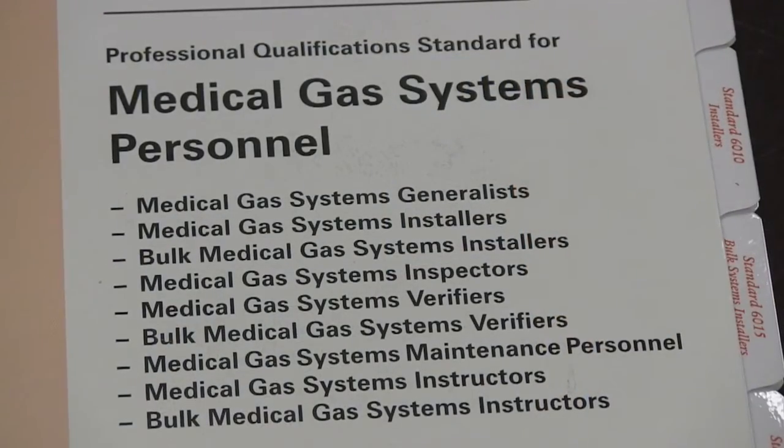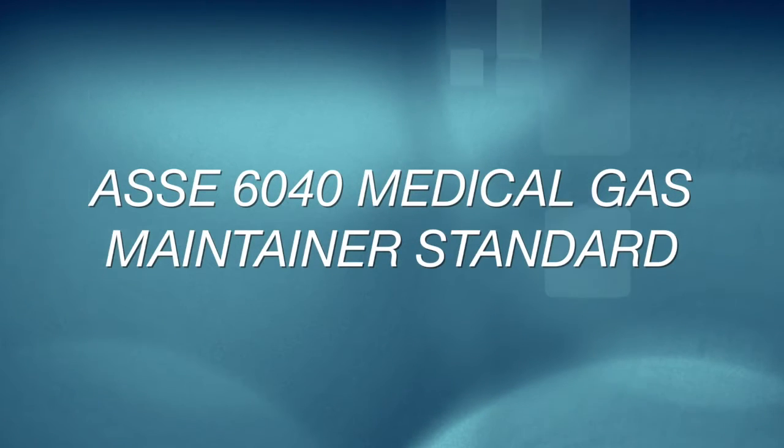There are three different qualification requirements for people maintaining medical gas systems. If your facility staff is maintaining your own medical gas systems, they are required to obtain training through your facility on the specific equipment installed, or by obtaining credentialing to the ASSE 6040 Medical Gas Maintainer Standard.